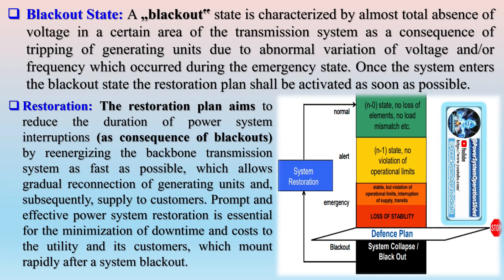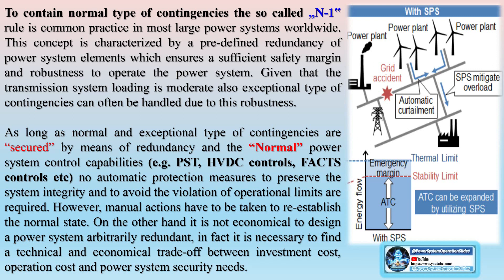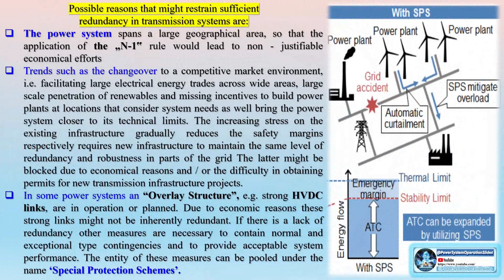The restoration plan aims to reduce the duration of power system interruptions by re-energizing the backbone transmission system as fast as possible, allowing gradual reconnection of generating units and subsequently supply to customers. Prompt and effective power system restoration is essential for minimization of downtime and costs to the utility and its customers. To contain normal type of contingencies, the N-1 rule is common practice in most large power systems worldwide, characterized by a predefined redundancy of power system elements ensuring sufficient safety margin and robustness.